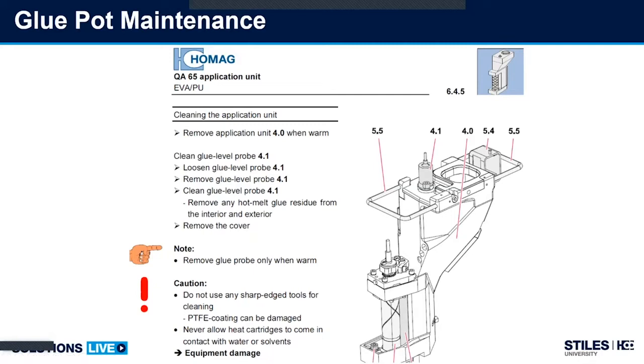Once I pull this probe out using gloves, I can then let it cool and roll the glue off the end of the probe. This will extend the life of the probe greatly. Once you char glue, once it gets black and chars onto this probe, it's very hard to recover and will eventually cause probe failure. So with this sensor, I'd recommend checking it at least once a month, depending on usage and how often you run.